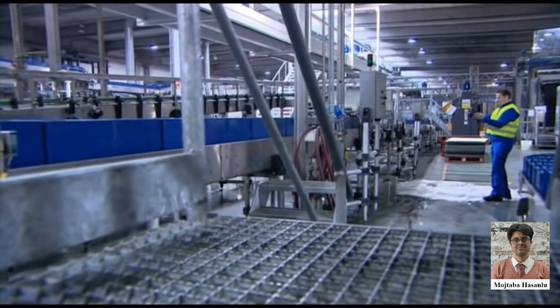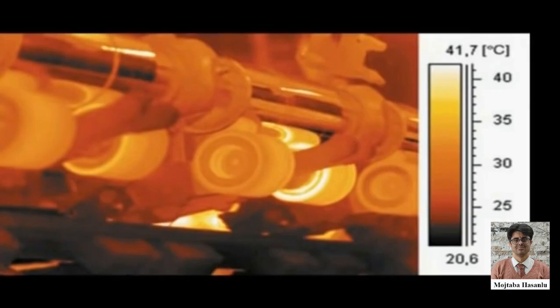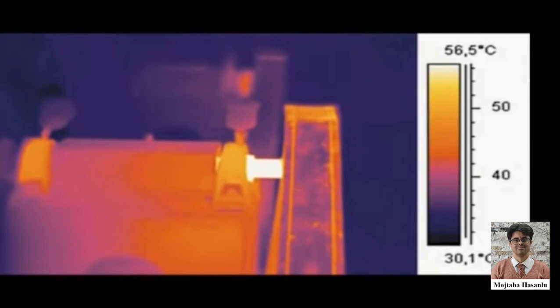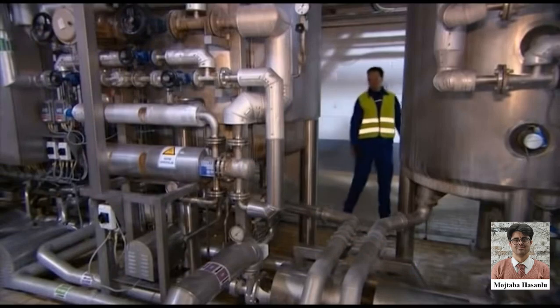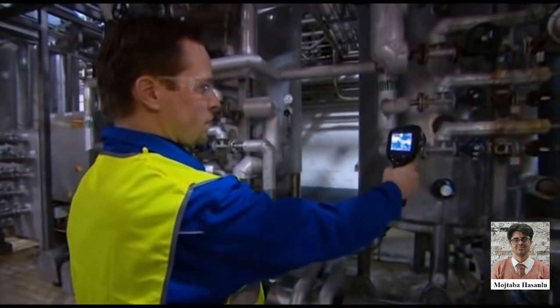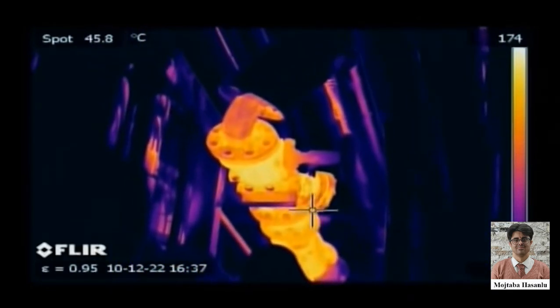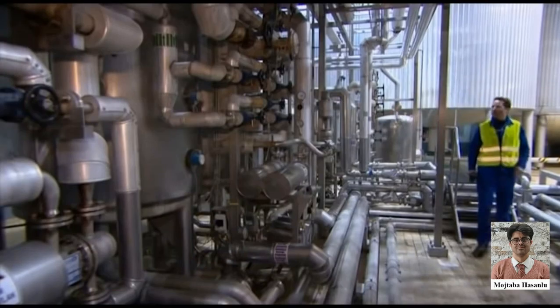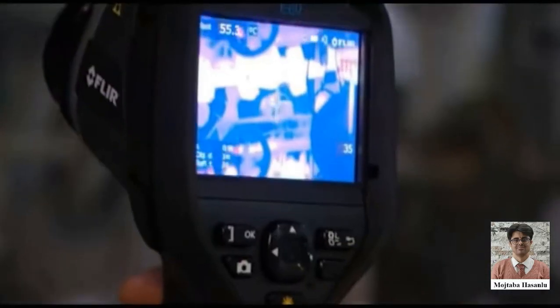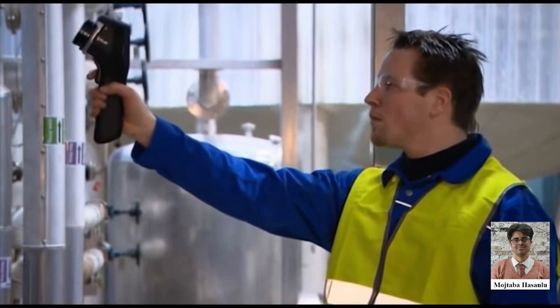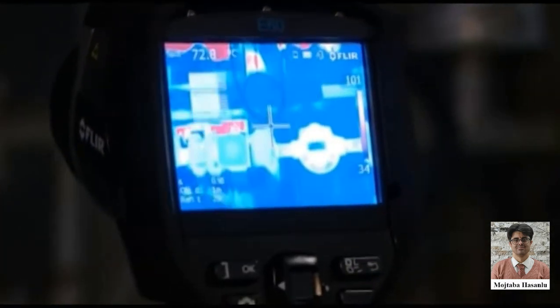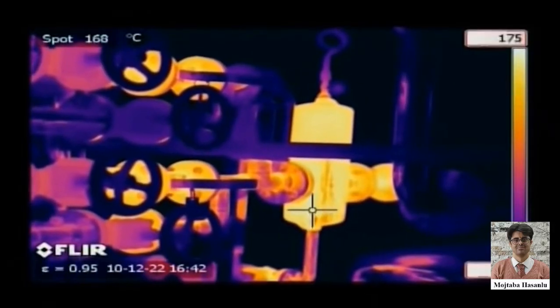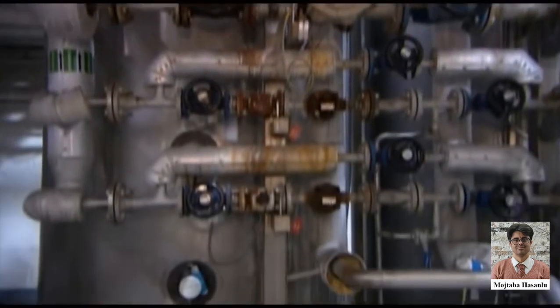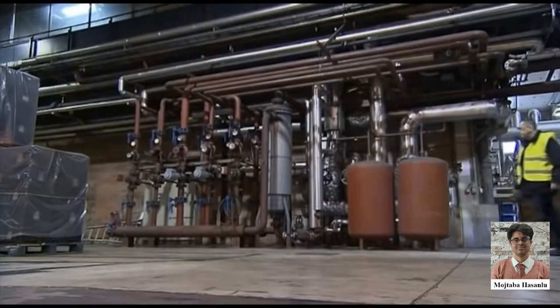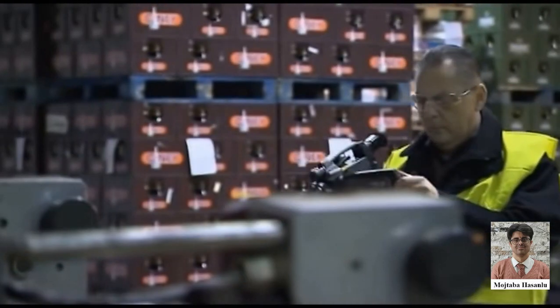Examples of faults that can be detected with thermal imaging are overheated motors, suspect rollers, overloaded pumps, overheated motor axles, hot bearings. Thermal imaging also gives valuable information about the condition of pipe, tube and valve insulation. A thermal imaging camera can quickly give an overview of the entire installation. There's no need to check each pipe individually. Thanks to analysis tools like spot meters, line profiles, areas, isotherms, and many more, potential problem areas will be clearly identified, and the repairs can be done before real and sometimes dangerous problems occur.